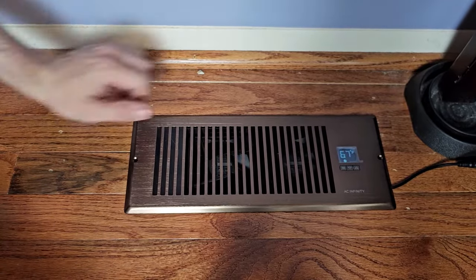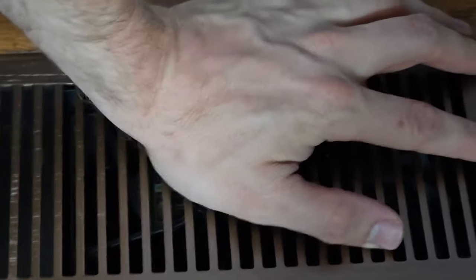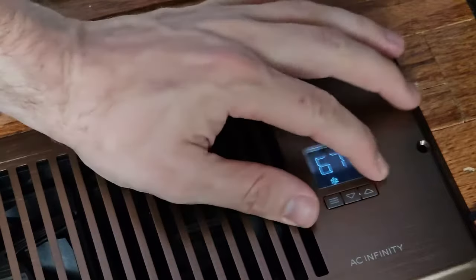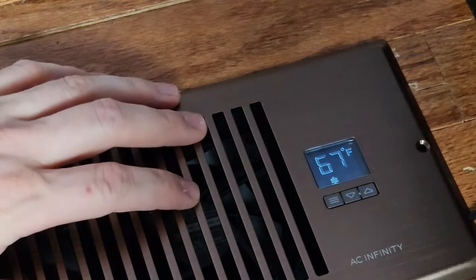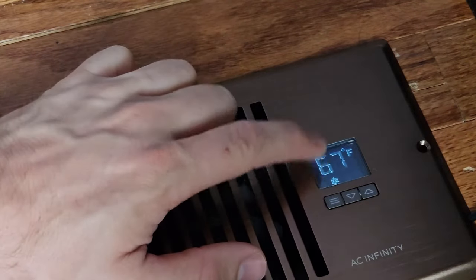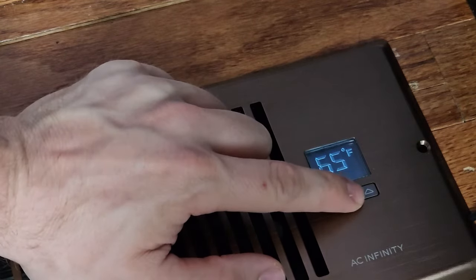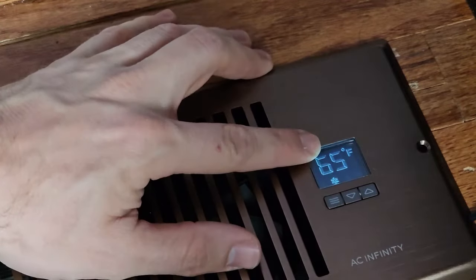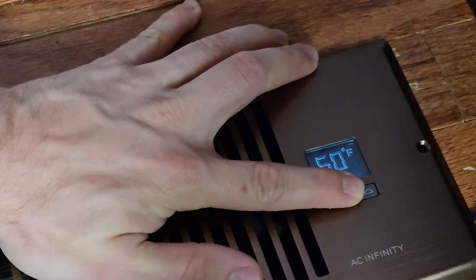Let's talk about the features. The first thing you can notice is we are in the snowflake mode — snowflake means we're in cooling mode. This fan is not going to turn on unless it detects a temperature at 67 degrees or above. We can adjust this. Most air conditioning systems aim to achieve a supply temperature of 20 degrees below the return temperature, so somewhere in the 50 to 60 degree range would be pretty normal.